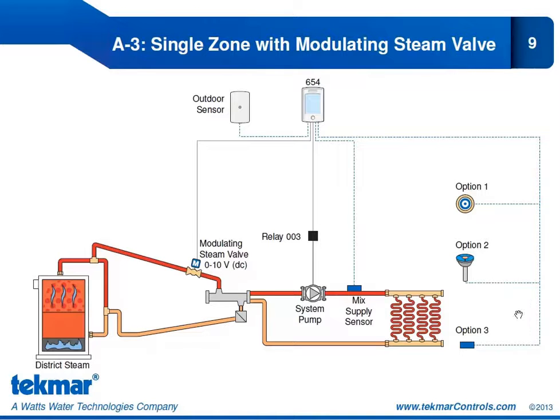But unless we combine it with option 3, we would have no way of controlling the slab temperature because we're not measuring it with the 095. If we combine option 2 with option 3 and install a slab sensor 072 or 073, then we do have the automatic start with time stop together with slab temperature control, which is our best option if we don't go with option 1 being the automatic snow ice sensor.